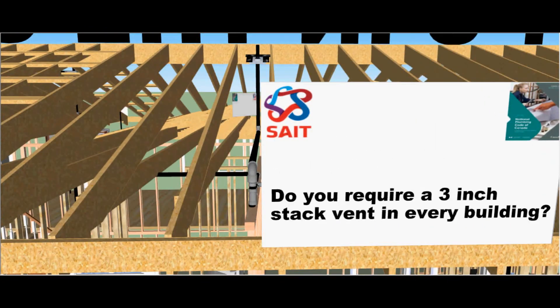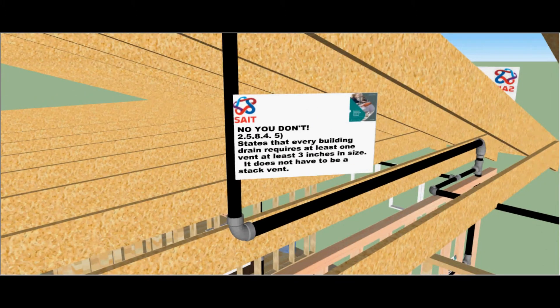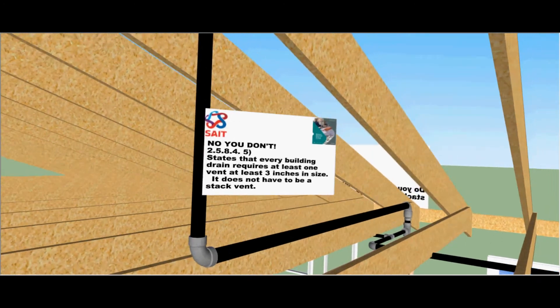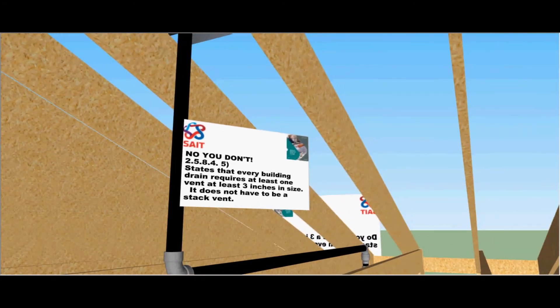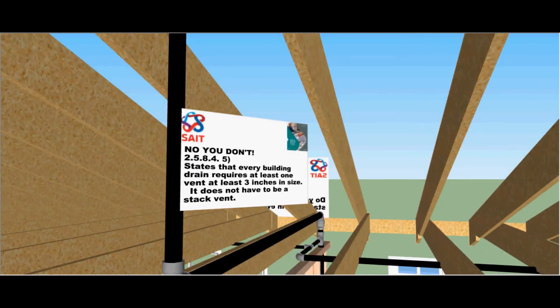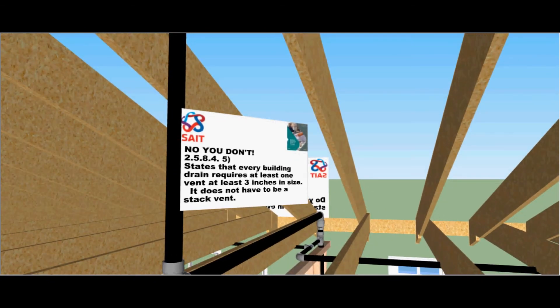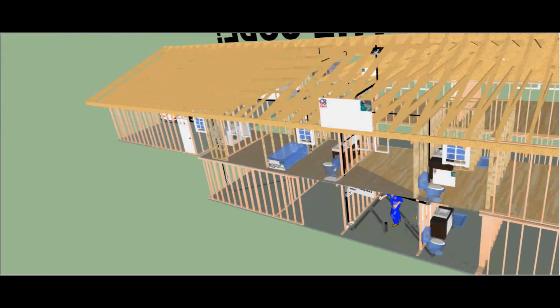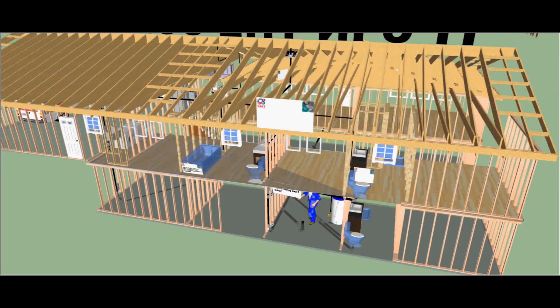Do you require a 3 inch stack vent in every building? No you don't. Clause 2584 subsection 5 states that every building drain requires at least one vent at least 3 inches in size. It does not have to be a stack vent. It could be a branch vent, a continuous vent, or any other type of vent as long as it's 3 inches in size.